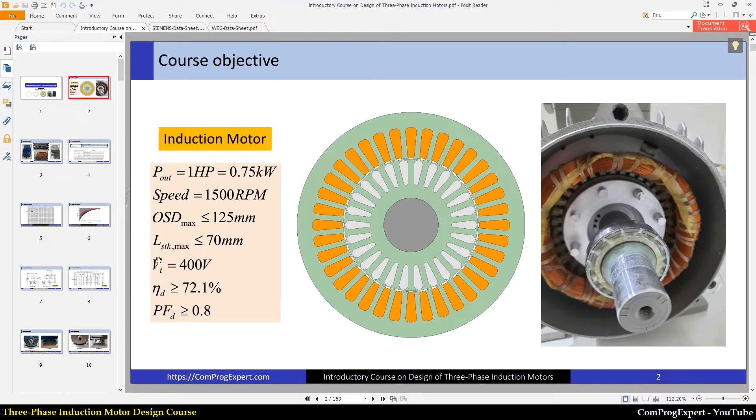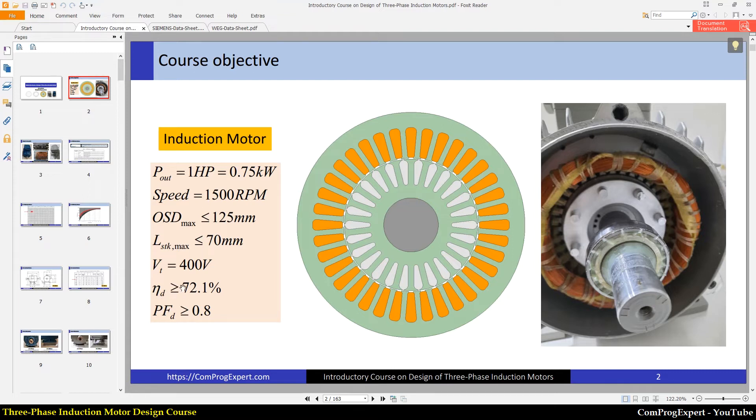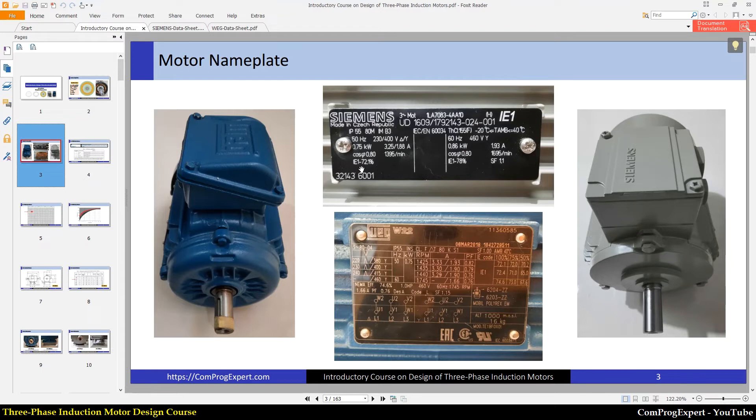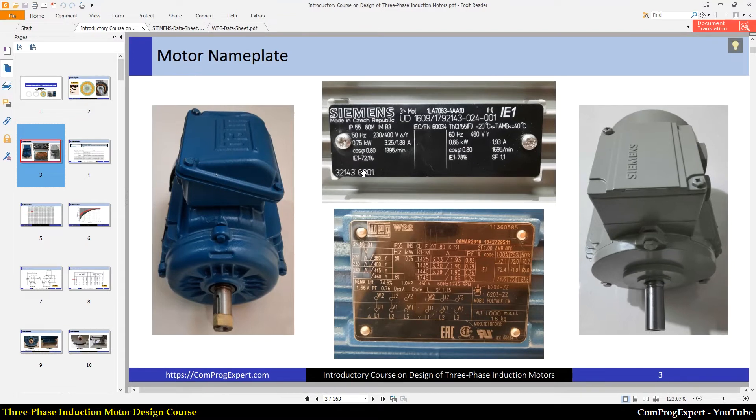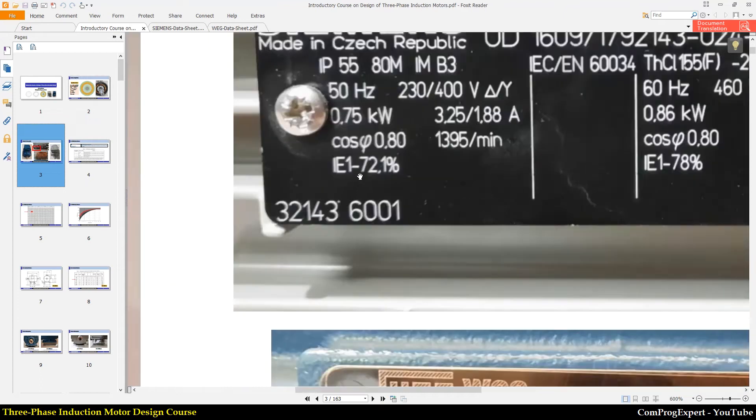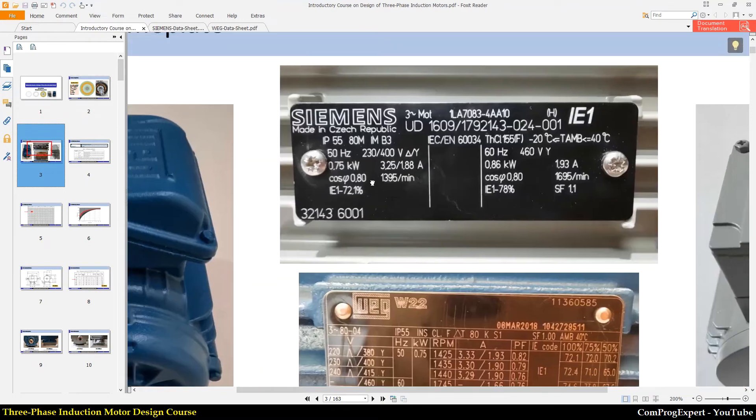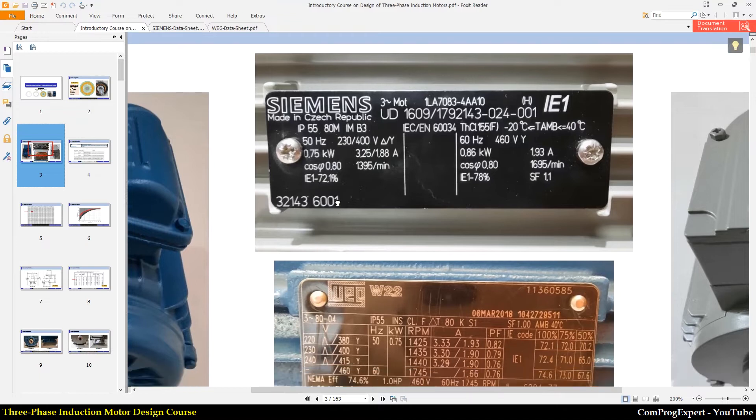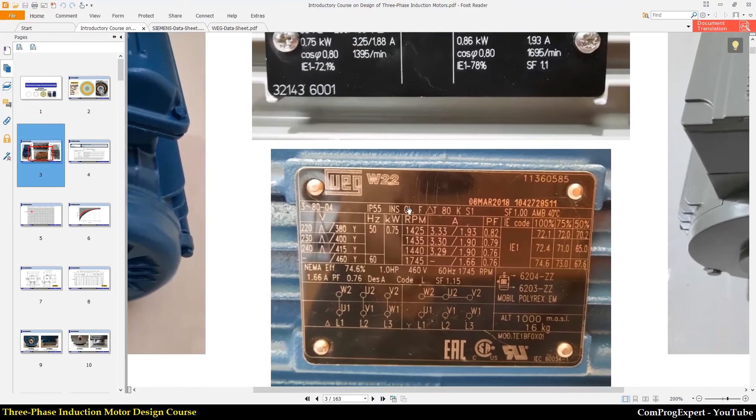The terminal voltage is 400 volts. The desired efficiency should be higher than or equal to 72.1%. The efficiency class of these two motors are the same and is actually IE1 efficiency class. You can see IE1 here. If I zoom right on nameplate of the Siemens motor, you can see the efficiency here, IE1.